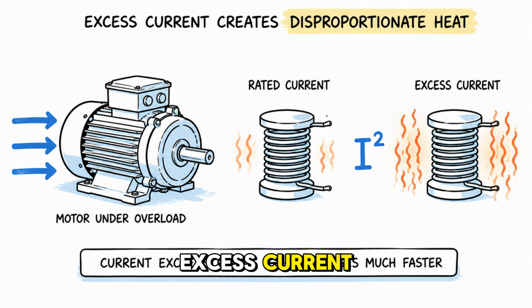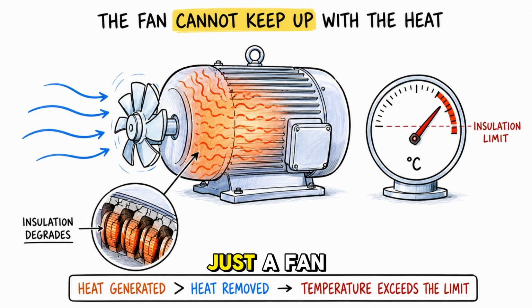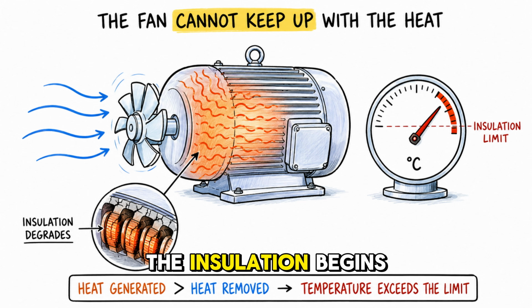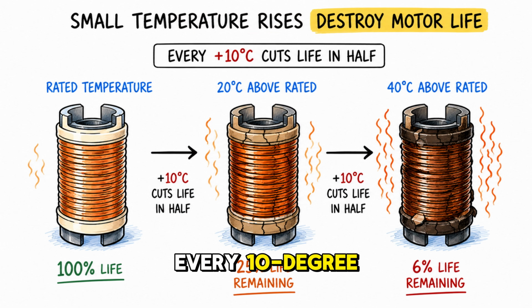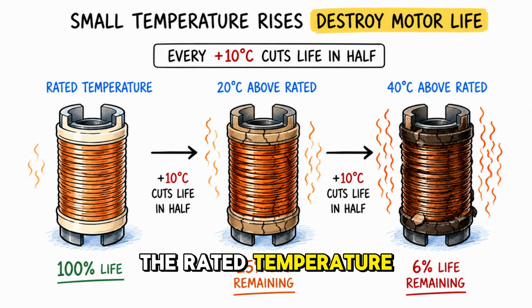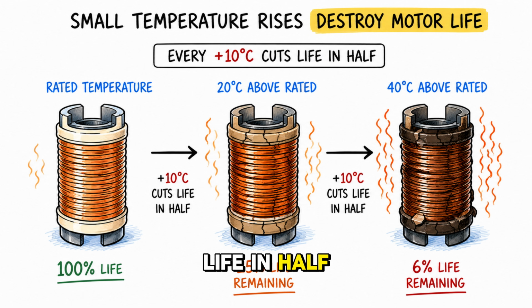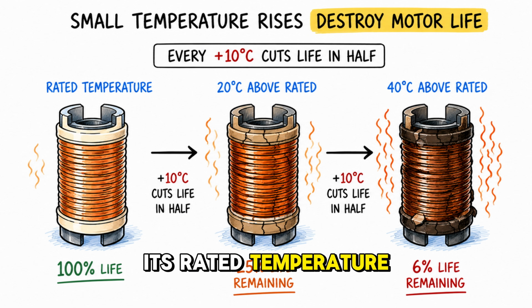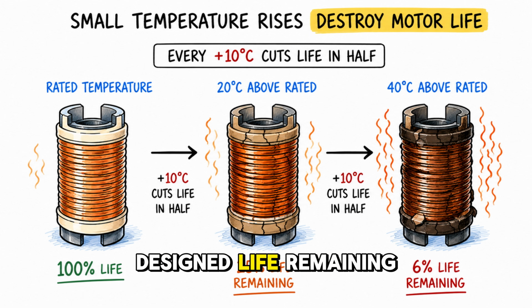Heat generation increases with the square of this excess current. The cooling system, which is usually just a fan mounted directly on the motor shaft, cannot remove heat faster than it is being generated. The winding temperature climbs straight past the insulation rating. The insulation begins to degrade. Every 10 degrees Celsius rise above the rated temperature cuts the insulation life in half. A motor running 20 degrees above its rated temperature loses 75% of its expected insulation life. A motor running 40 degrees above its rated temperature has only 6% of its designed life remaining.